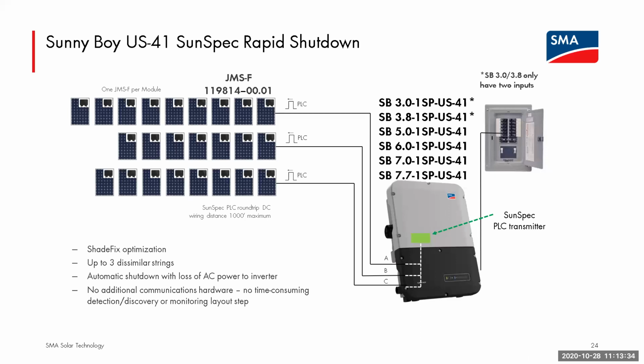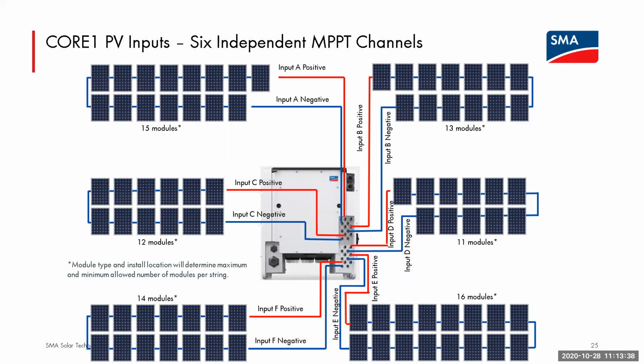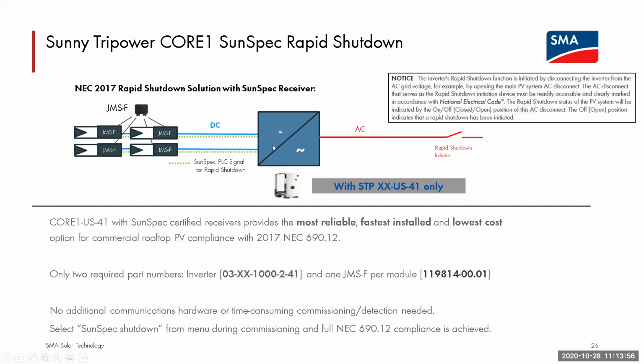Jump over to a little bit bigger commercial system. Again, this is just showing the flexibility of the Core 1 and that you have 6 independent MPPT channels. You can have long strings, short strings, and that SunSpec transmitter is built right into the inverter, which is shown here on this slide. Again, sending that keep alive signal over the DC home run lines to the SMA rapid shutdown receivers, whether that's the JMS-F, the TS4R-F, and in the future, we foresee adding some other compatible SunSpec shutdown receivers. It's a real simple solution, not only easy to install, but extremely easy to commission. Again, we are not having to map these devices. It's an install, code compliant, highly reliable system.